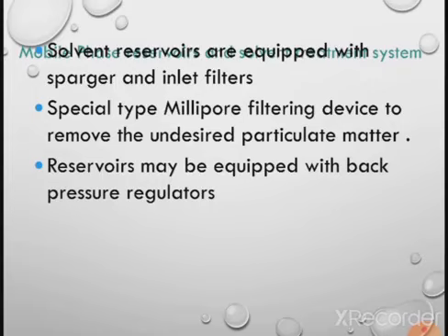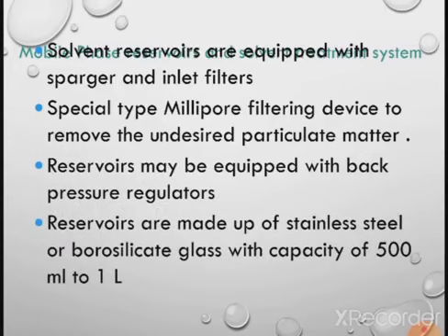Reservoirs are made from stainless steel or borosilicate glass, with different capacities from 500 ml to 1 liter. In some cases they may be made of reinforced nylon, and they are coated with an inert layer so that they do not interact with the mobile phase.